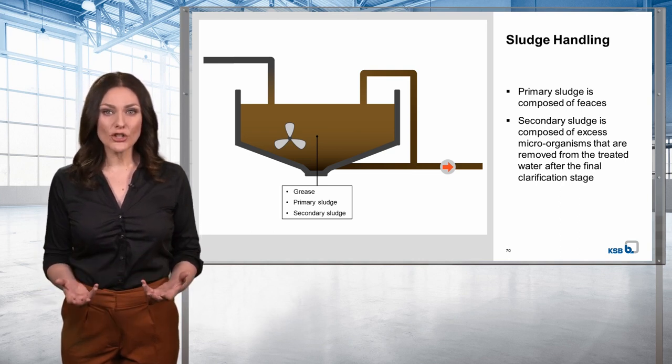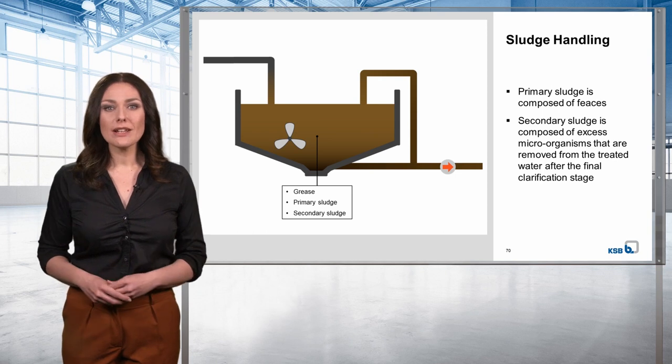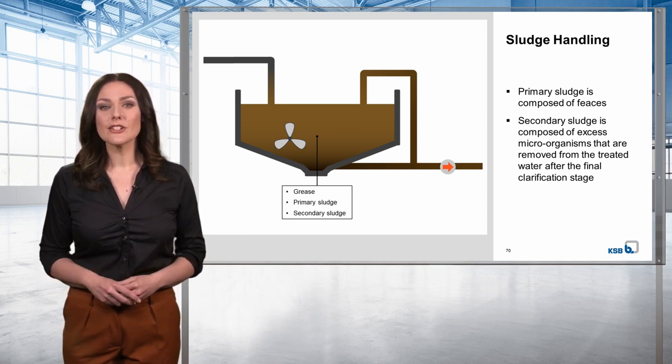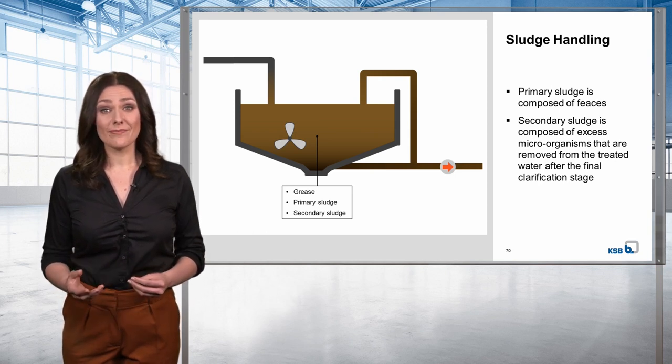In sludge treatment, water is removed from the sludges — the sludges thicken. The thickening process reduces the volume of the sludge to be treated and increases its dry solids content, abbreviated to DSC, for example from 1% to 3%.